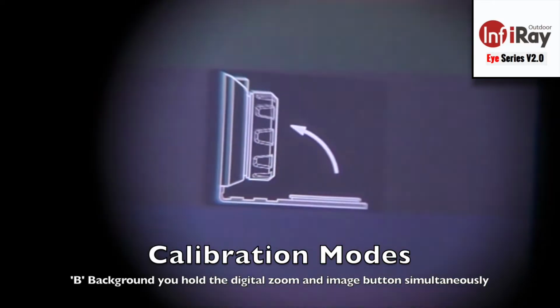Whereas if you go into the long menu and you select B for background, when you do that same function of holding the digital magnification and image capture, it's going to prompt you to place the lens cap over the shutter, and it's going to calibrate quietly without the shutter, the lens cap taking the place of the shutter. I prefer the shuttered calibration just because it's quick and simple. You don't have to cover the front of the unit, but the silent background function is there for you if you so choose. Alright, finalizing the long menu here.